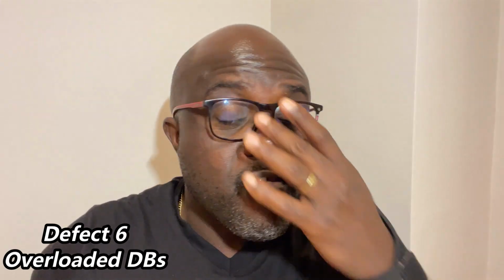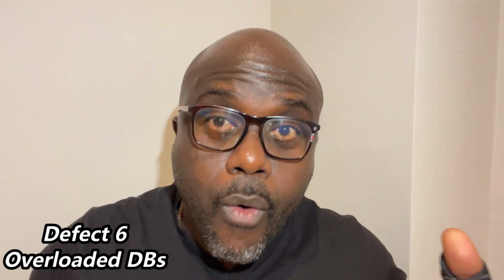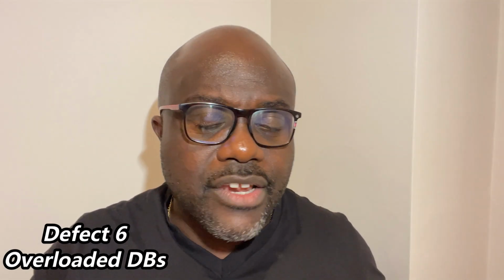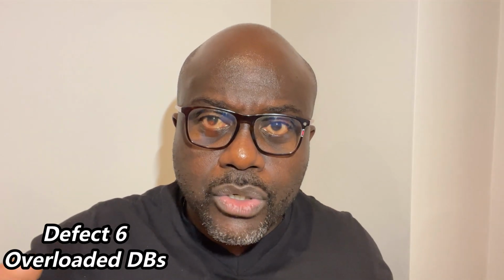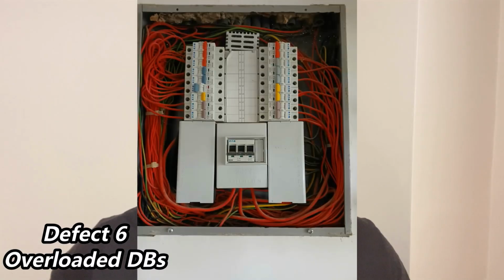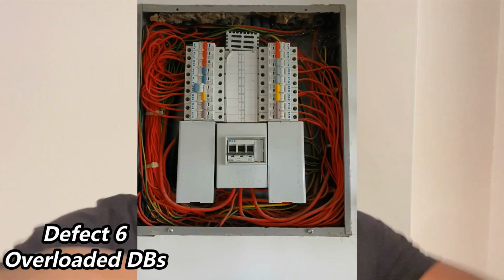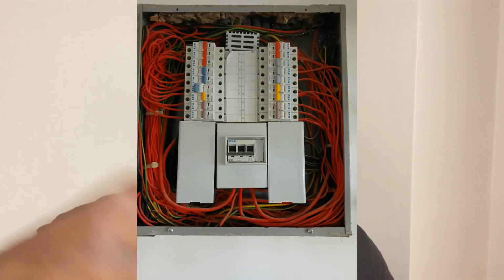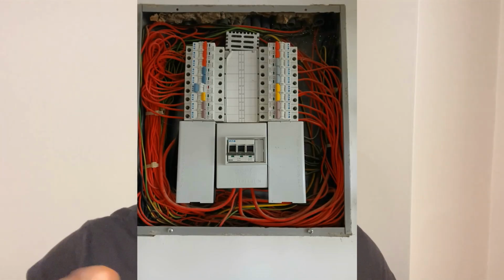Defect number 6, very, very common. Some pictures on your screen are from various home inspections we've done. It seems to be a common thing that a lot of electricians in Ghana don't count the number of circuits before they buy the distribution board. It is very common to see a distribution board in Ghana that is completely overloaded, with 2 or 3 circuits going to one breaker. Not the way to go.